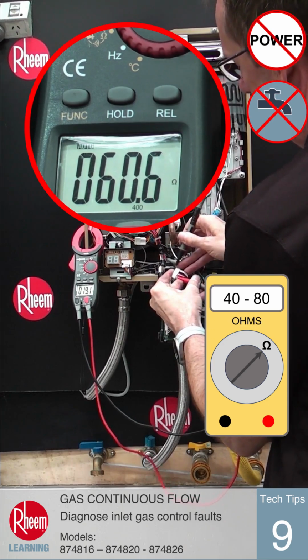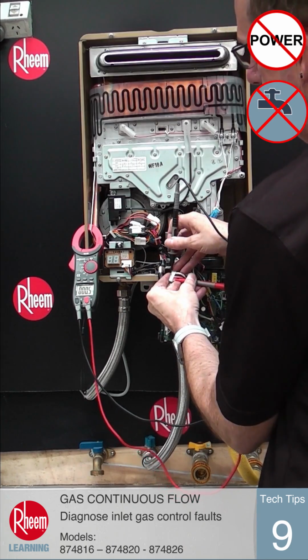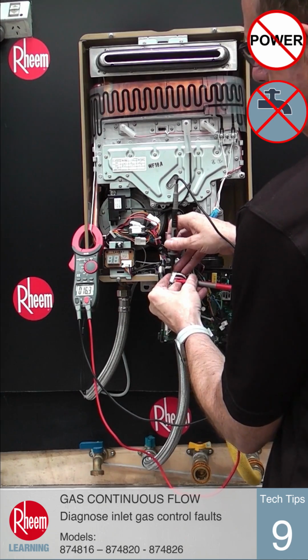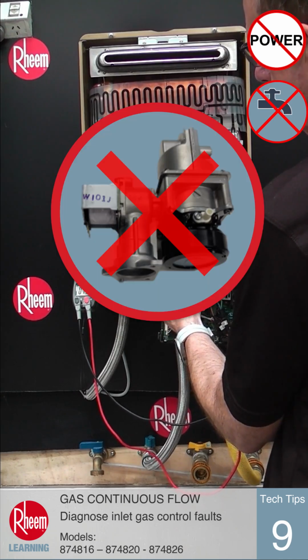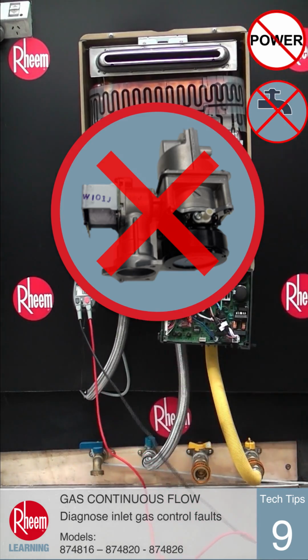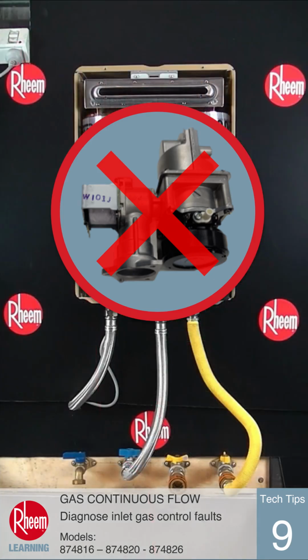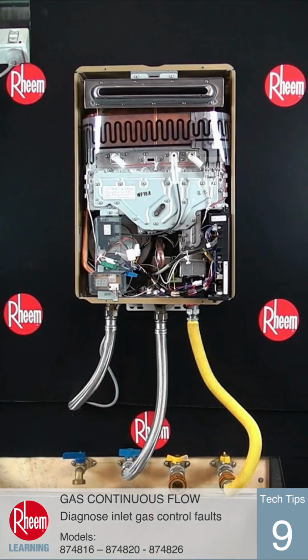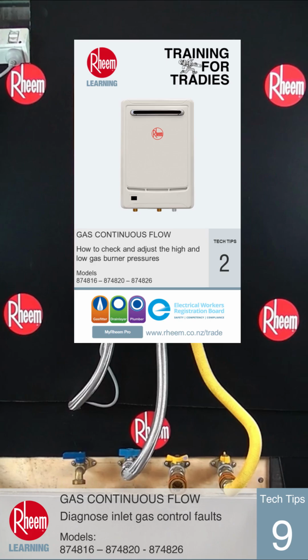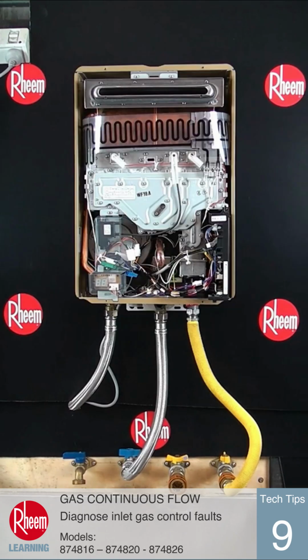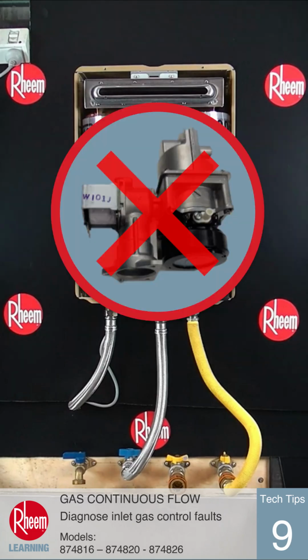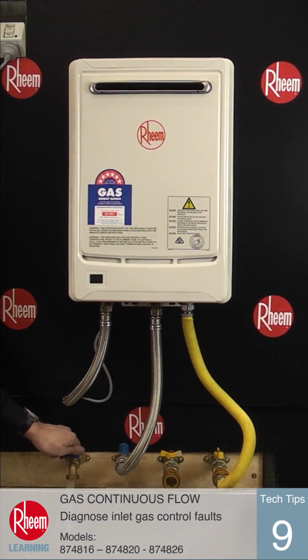If the resistance is not correct or is open circuit, check the wiring connections at the PGFR. If these are all good, the PGFR is faulty, so the inlet gas valve assembly should be replaced. If the resistance is correct and you have already tried setting the burner pressures as described in Tech Tips number 2 and adjustment was not achieved, the PGFR has a mechanical fault and will still need to be replaced.